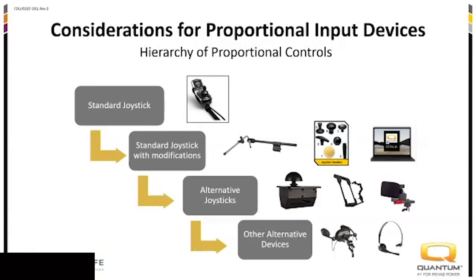There are really three categories of modifications for the standard joystick. One is changing the handle or top shape — power wheelchair manufacturers allow you to remove the standard handle and put on different shapes like a goalpost or a ball shape. We can also change the mounting, moving where the device is positioned. And my favorite part is the programming — there are specific programming features where, maybe they're not able to utilize the standard joystick, but with certain programming changes, they can.